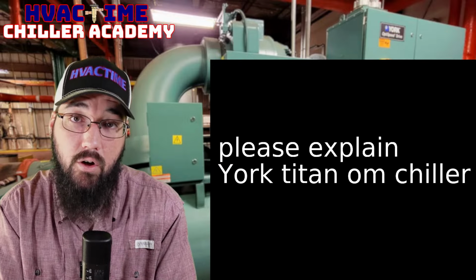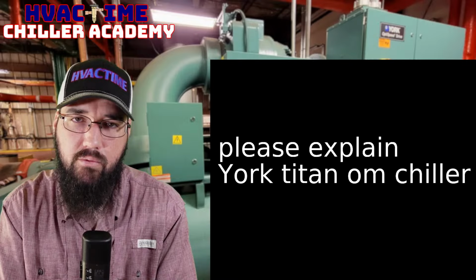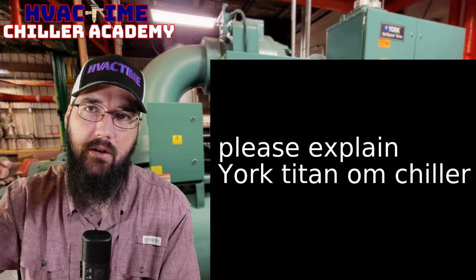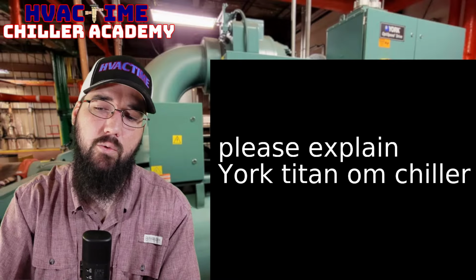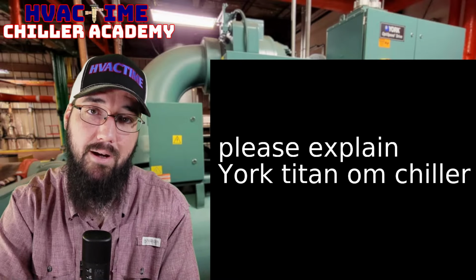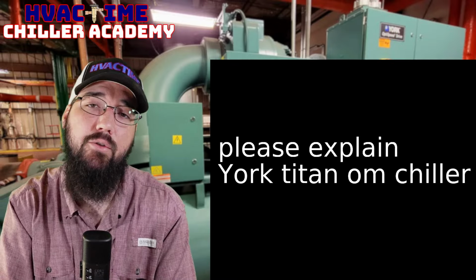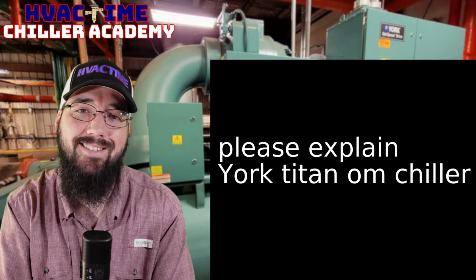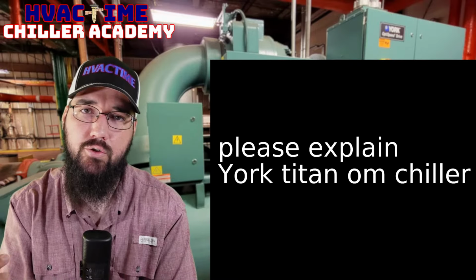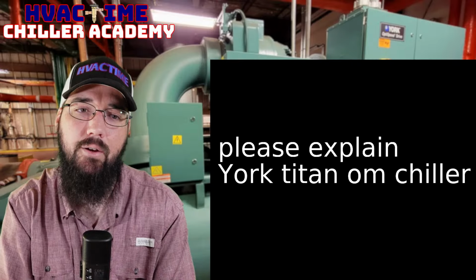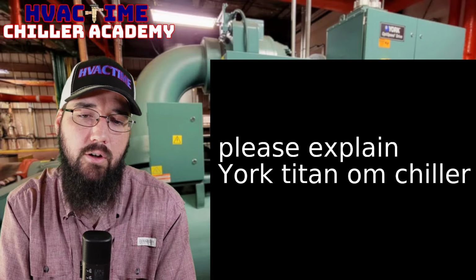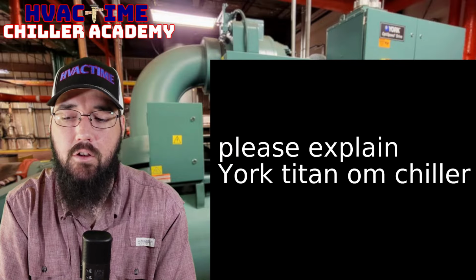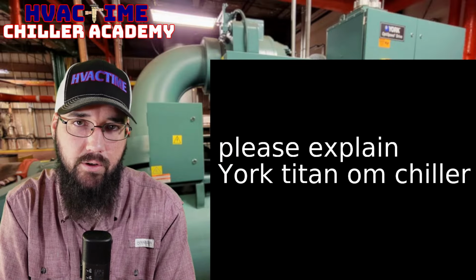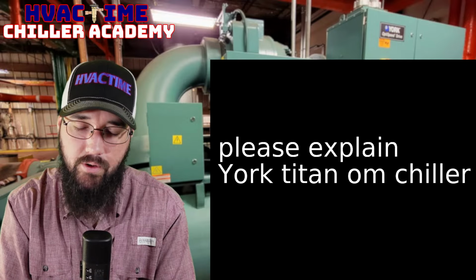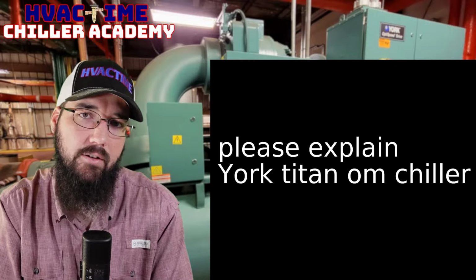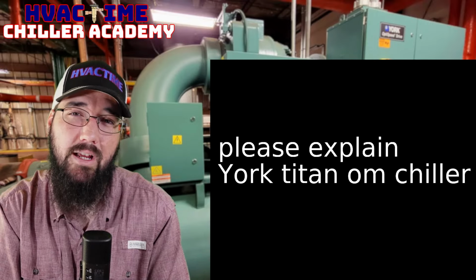So you'll have the compressor on the ground, and you'll have the suction pipe. The evaporator and condenser will still be stacked, but your suction and discharge pipe will actually pipe down into the compressor. They look kind of funny compared to what we normally expect. We normally expect a fairly tight machine where we've got a short suction, short discharge, kind of like the one you see behind me. That's a YK, right? That's what we would consider a normal look for a centrifugal chiller in today's market, right? Well, these OMs just look odd compared to the smaller tonnage machines that are more of a central package.